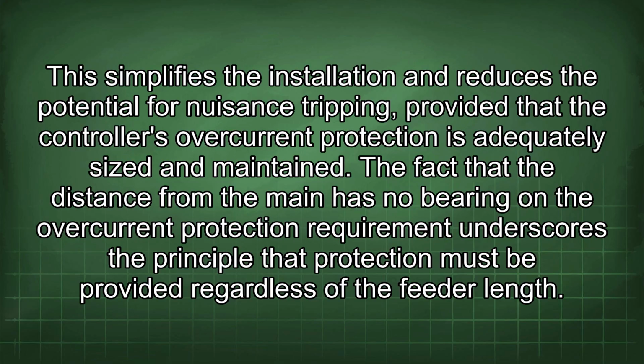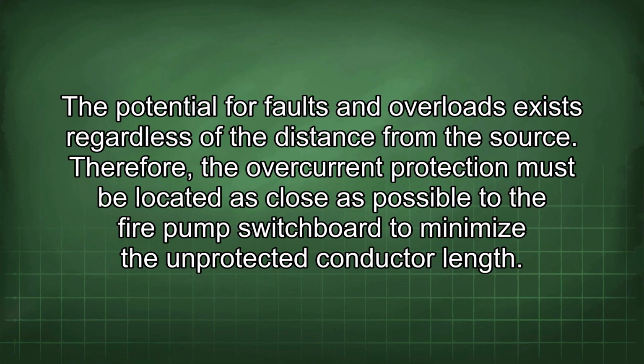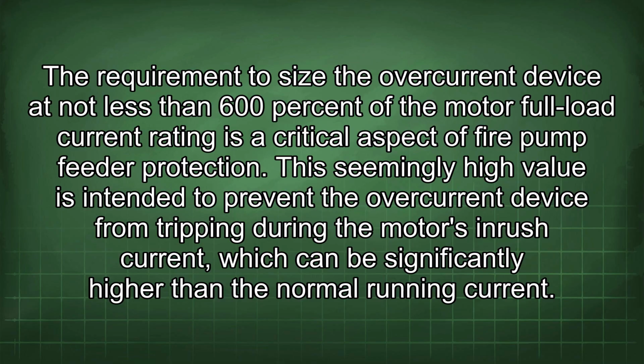This simplifies the installation and reduces the potential for nuisance tripping, provided that the controller's overcurrent protection is adequately sized and maintained. The fact that the distance from the main has no bearing on the overcurrent protection requirement underscores the principle that protection must be provided regardless of the feeder length. The potential for faults and overloads exists regardless of the distance from the source. Therefore, the overcurrent protection must be located as close as possible to the fire pump switchboard to minimize the unprotected conductor length. The requirement to size the overcurrent device at not less than 600% of the motor full load current rating is a critical aspect of fire pump feeder protection.